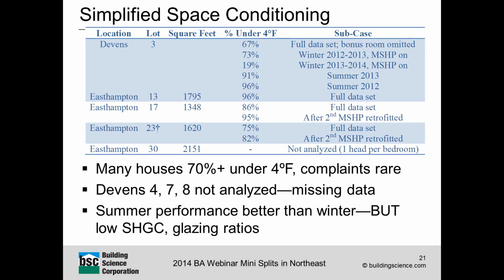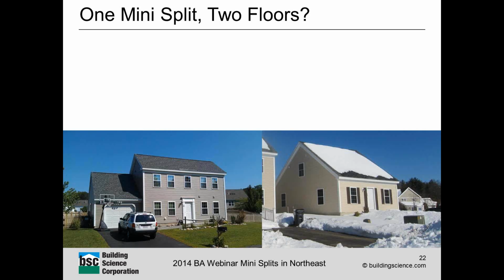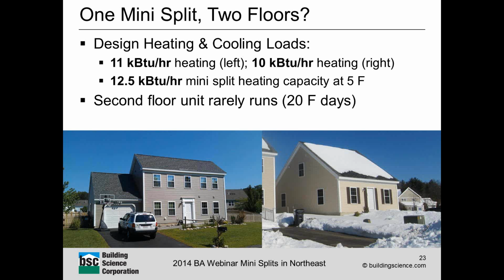So one of the problems we had was houses with 2 stories and 1 mini-split heat pump. This shows a couple of houses that are on the smaller end of the production that they put out, in the 1,200 to 1,500 square foot range. So design loads are nice and small, 10 to 11 kBTU per hour, which is well within the design capacity of what these mini-split heat pumps can put out, even at design conditions. The other thing that the builder pointed out is he's been working with these types of mini-splits for a long time. He noticed that during the winter, typically the second floor unit barely runs. So what he was thinking is, look, the 1 mini-split should do it on these houses. Let's go ahead and run it that way. So, good experiment. Let's try it.